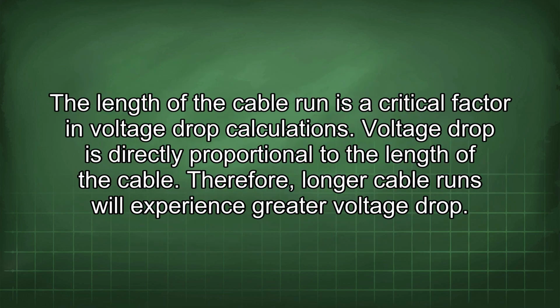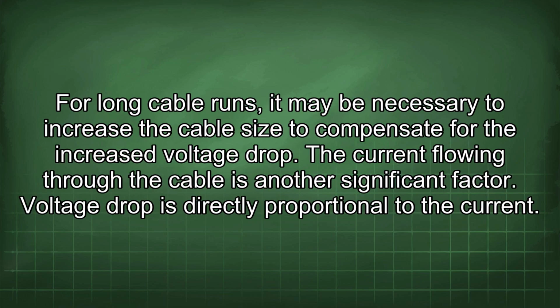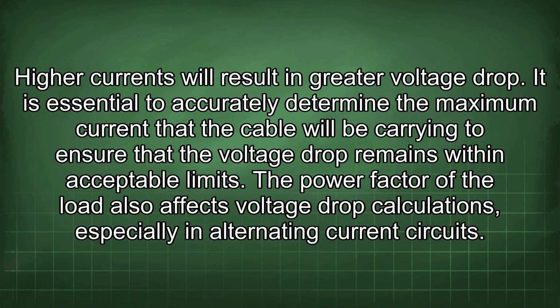The length of the cable run is a critical factor in voltage drop calculations. Voltage drop is directly proportional to the length of the cable. Therefore, longer cable runs will experience greater voltage drop. For long cable runs, it may be necessary to increase the cable size to compensate for the increased voltage drop. The current flowing through the cable is another significant factor. Voltage drop is directly proportional to the current. Higher currents will result in greater voltage drop. It is essential to accurately determine the maximum current that the cable will be carrying to ensure that the voltage drop remains within acceptable limits.